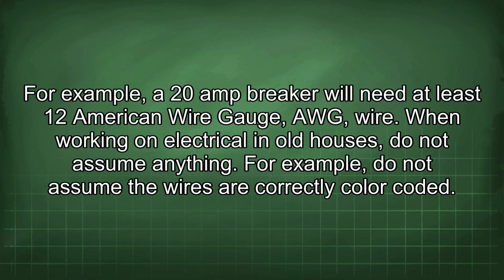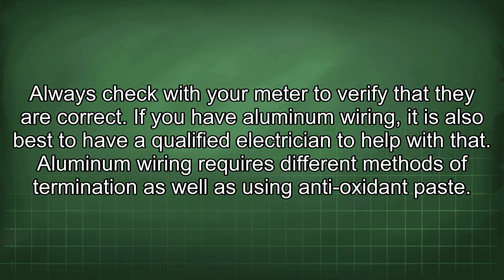When working on electrical in old houses, do not assume anything. For example, do not assume the wires are correctly color-coded. Always check with your meter to verify that they're correct. If you have aluminum wiring, it is also best to have a qualified electrician to help with that. Aluminum wiring requires different methods of termination as well as using antioxidant paste.